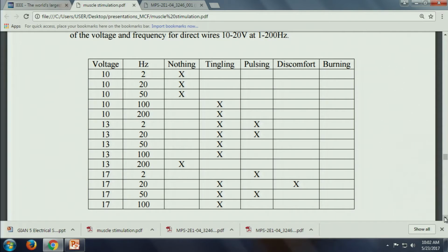When you say burning, there are two things that can happen. Number one, there is a burning feeling which remains subsequent to the passage of the current. Number two, you physically observe a portion of the tissue getting burned. You don't allow that much, because as soon as it burns, they will take it off, or I will remove it or switch off the equipment. That's why I always let two people do this, I don't want one person. So one has to be monitoring.